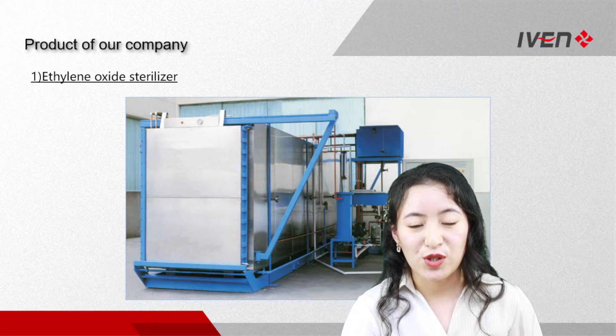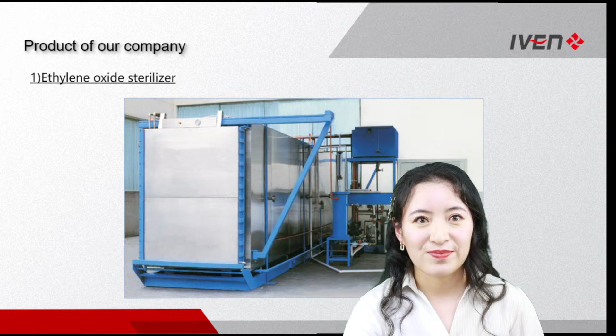And which kind of product will be suitable for this method? It will be some medical equipment, some medical disposables, and plastic products. And please pay attention that items containing chlorine and items that can absorb ethylene oxide are not suitable for this method. Here we have two sterilizers to introduce to you. First is the ethylene oxide sterilizer. Second is the VHP type room temperature sterilization transfer cabinet.